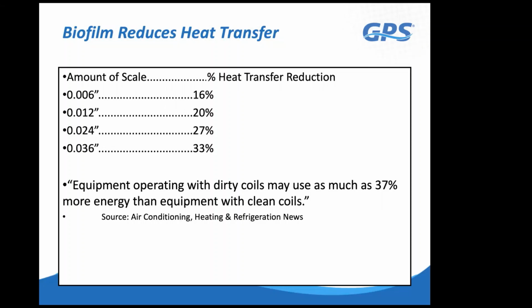And so with this technology, we're able to keep the coils clean, which impacts your heat transfer. So we're going to keep the load on the chiller down versus allowing the biofilm to hinder that heat transfer. In addition to the heat transfer savings, you also get savings in the energy of the fan because the fan has to work less hard to pull the air through the coil.